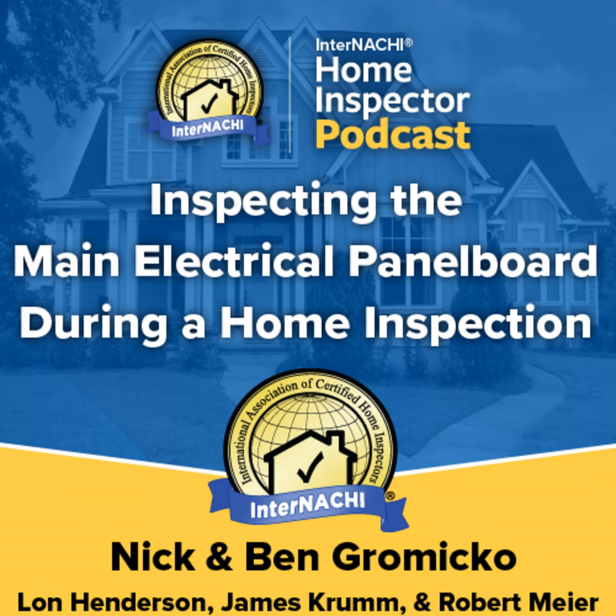Meter bases can be configured with the panel board location in several ways. The main disconnect can be installed at either the meter base or the breaker panel. A common arrangement may be where a meter base is only on the outside of the house and the service entrance conductors are run to the meter base and continue to a panel board inside the house. This panel inside the house may be called in common usage, but not in code, a main breaker panel, because the main breaker or main disconnect is installed in or is part of the panel board, integrated, along with the final branch circuit overcurrent protective devices, or breakers.